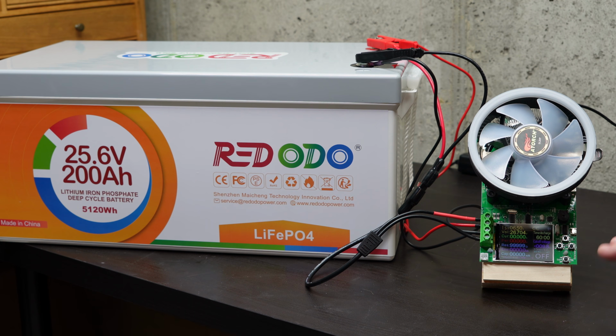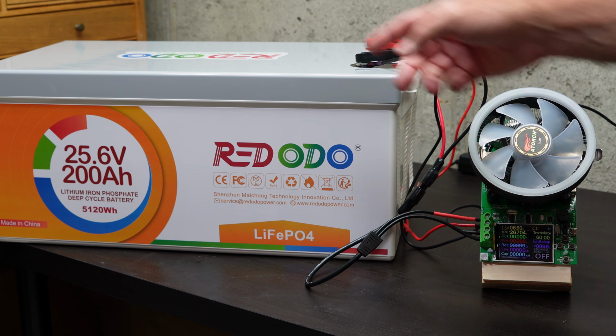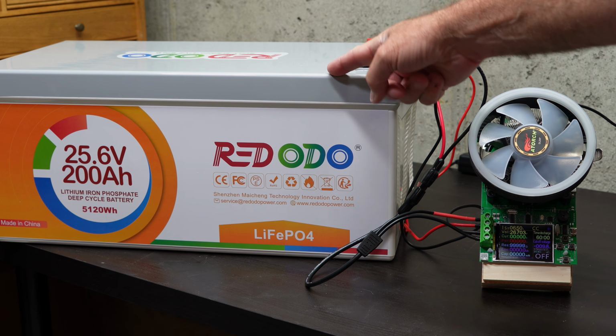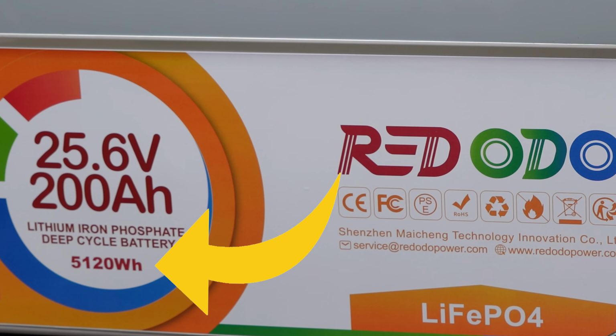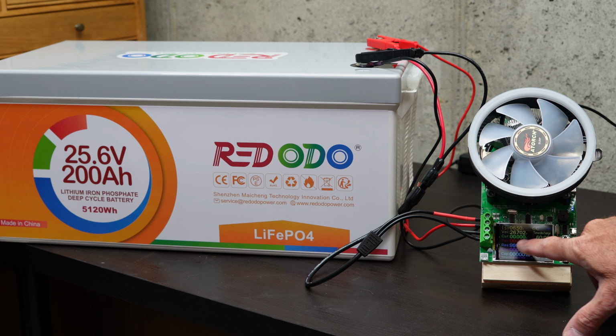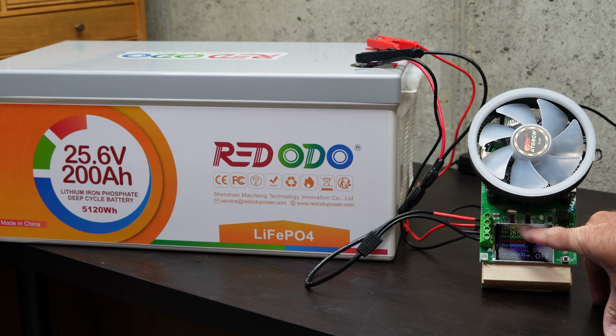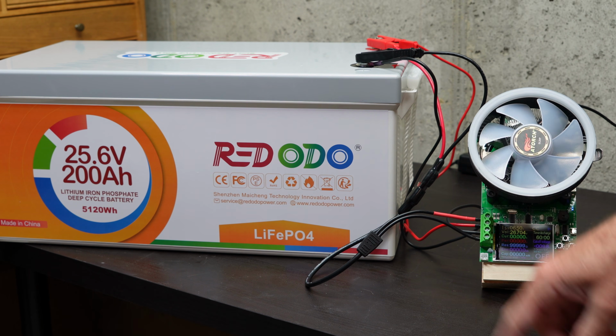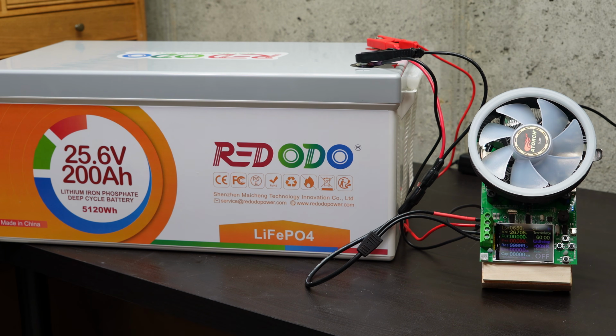We are going to do a capacity test on this 200 amp hour 24 volt battery. On the left, it's got a rated watt hour capacity of 5,120 watt hours. This is reading 26.7 volts right now, so it should be fully topped off. I'm only going to be able to pull about 6.5 amps, which is about 173 watts, and that's going to take somewhere around 30 hours. So I'm going to get this test running and see what the actual usable capacity comes out of this box, and how that compares to the rated 5,120 watt hours.